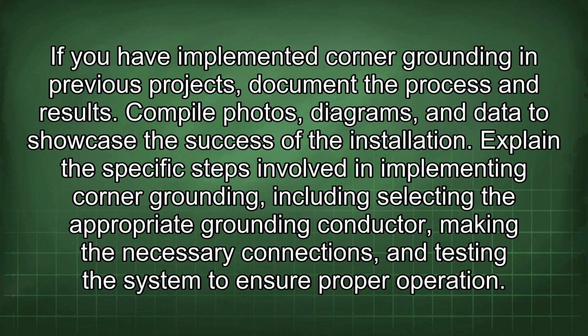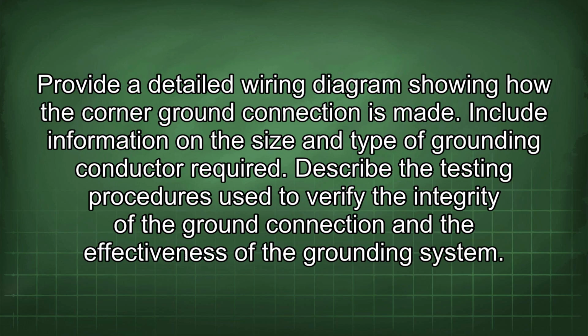Explain the specific steps involved in implementing corner grounding, including selecting the appropriate grounding conductor, making the necessary connections, and testing the system to ensure proper operation. Provide a detailed wiring diagram showing how the corner ground connection is made. Include information on the size and type of grounding conductor required. Describe the testing procedures used to verify the integrity of the ground connection and the effectiveness of the grounding system.